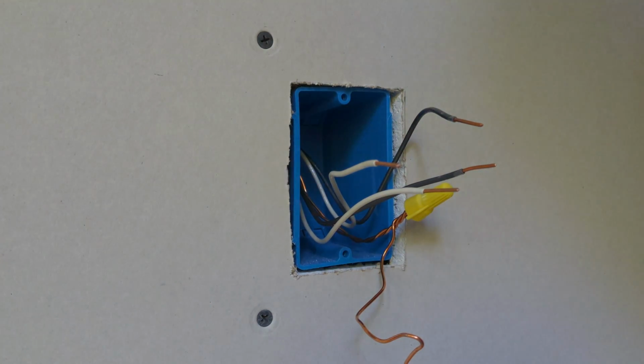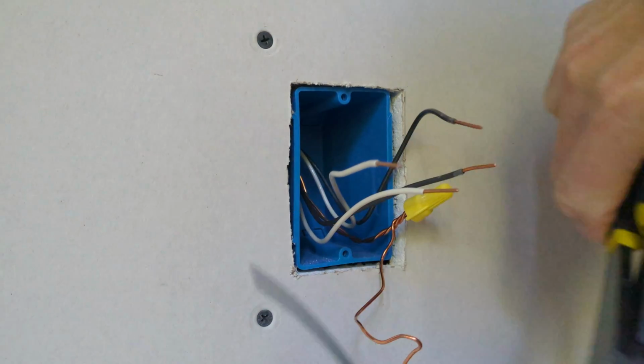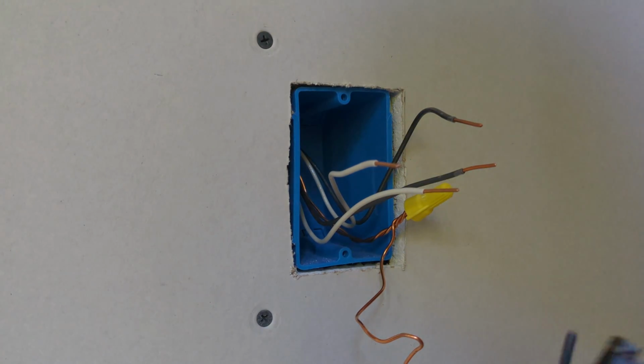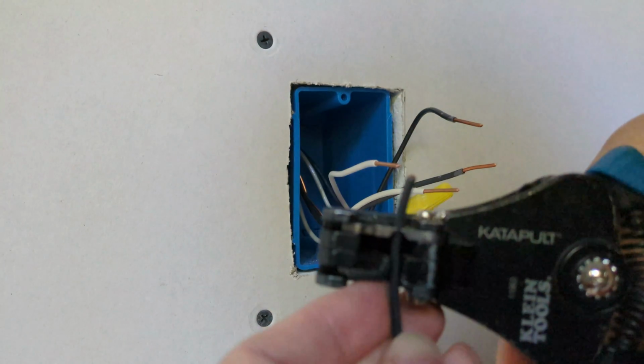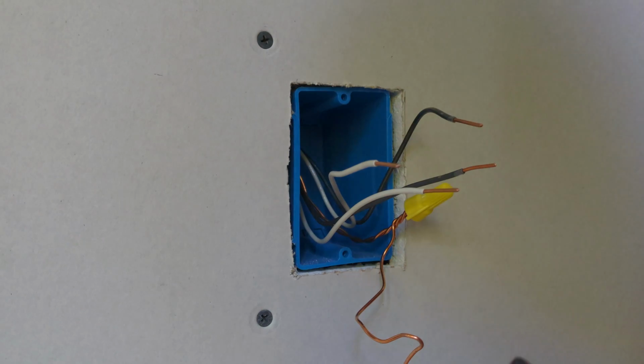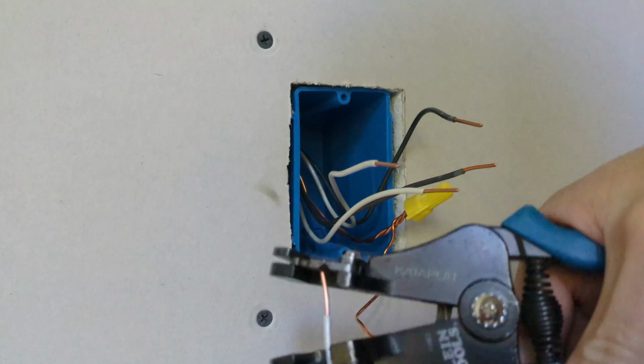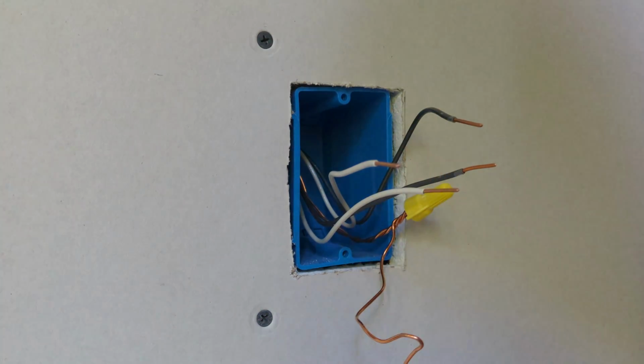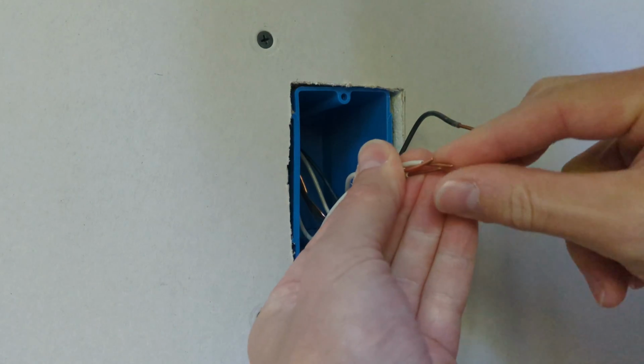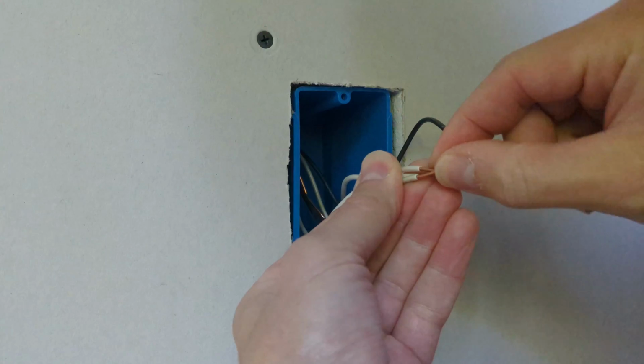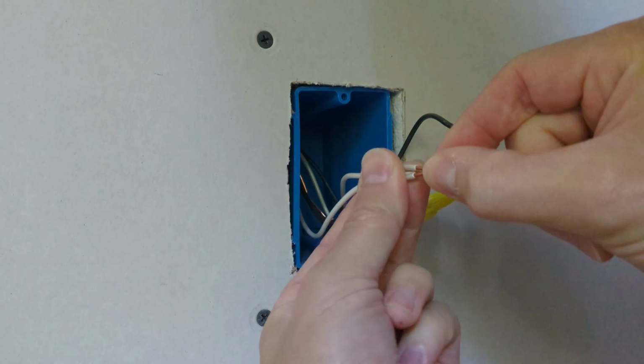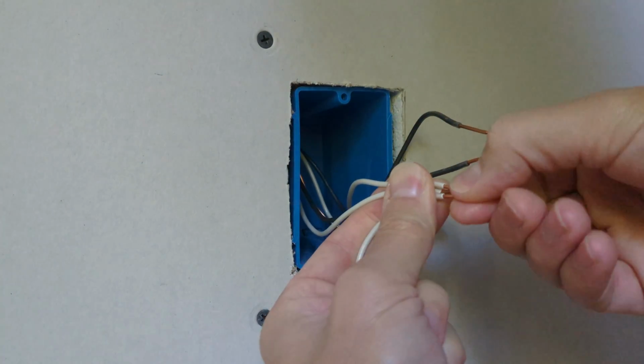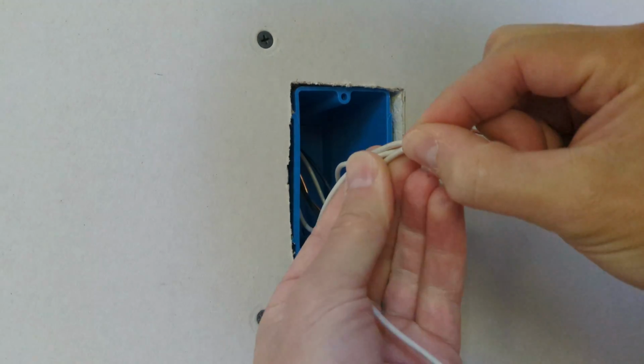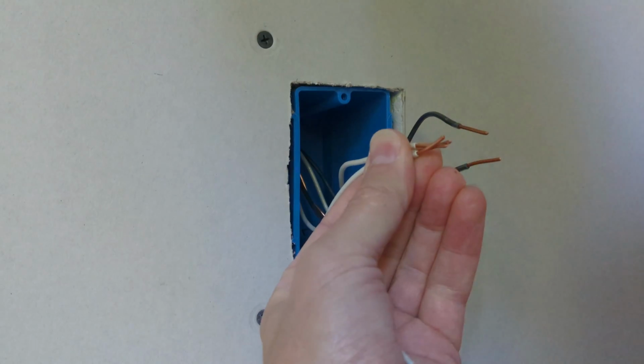Cut some lengths for neutral and hot pigtails and strip the ends of those as well. They'll tie the 3 neutrals together. One of them is power coming in. Another one in the box is the power going out over to the next outlet. And this pigtail that I'm adding here will be the power to this outlet in this box.